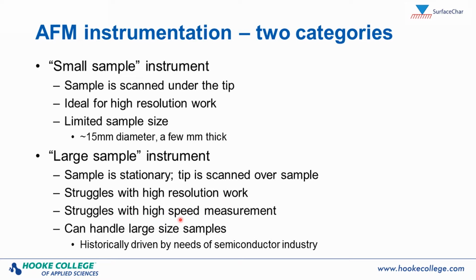It can also struggle with high-speed measurements because the samples can be very big. One of the biggest pros of a large sample instrument, obviously by its name, is that it can handle large sample sizes. This has historically been driven by the needs of the semiconductor industry, where they now have wafers that are a couple hundred millimeters in diameter, which clearly will not fit into a small sample instrument for the kind of critical device measurements I mentioned previously with the narrow trench mode.